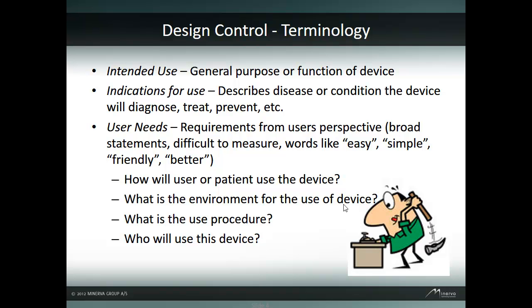User needs are requirements from the user's perspective, typically broad statements that are difficult to quantify or measure. They use words like easy, simple, friendly, or better. For example, the device must be easy and simple to operate. To get user needs, ask questions like: How will the user or patient use the device? What is the use procedure? What is the device use environment?